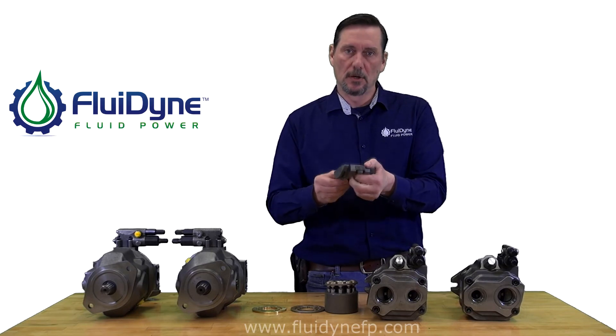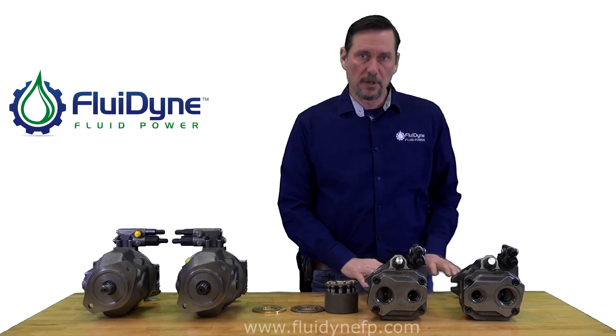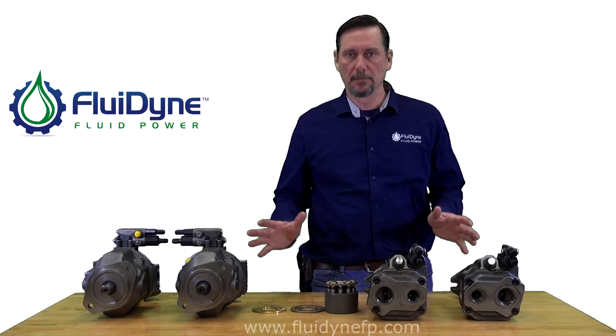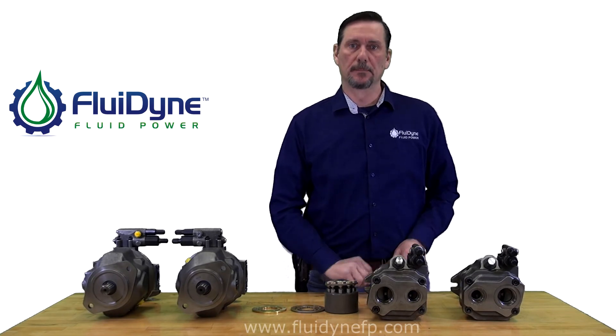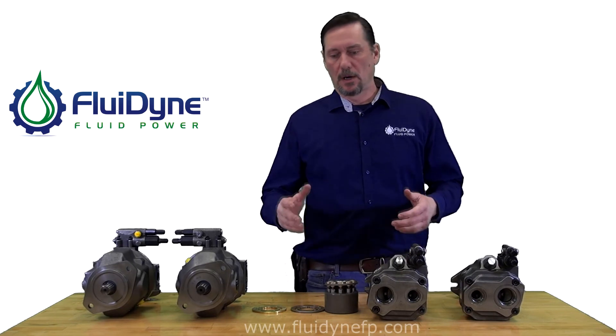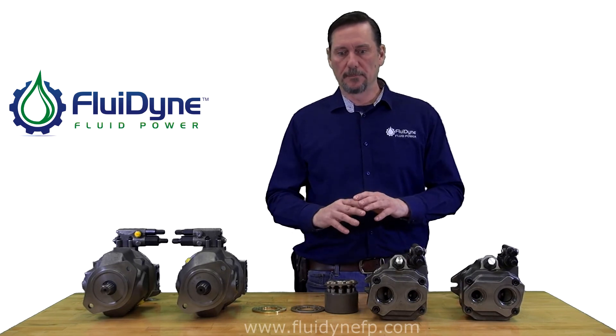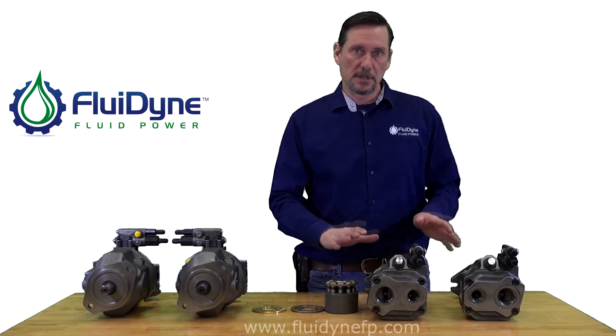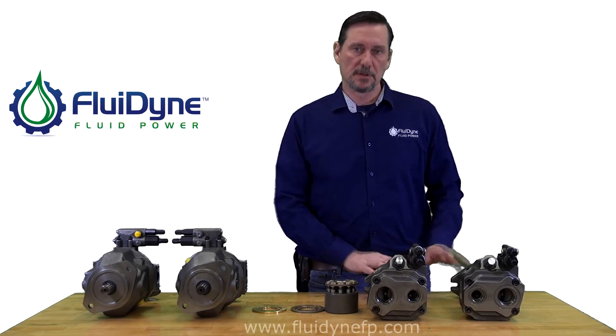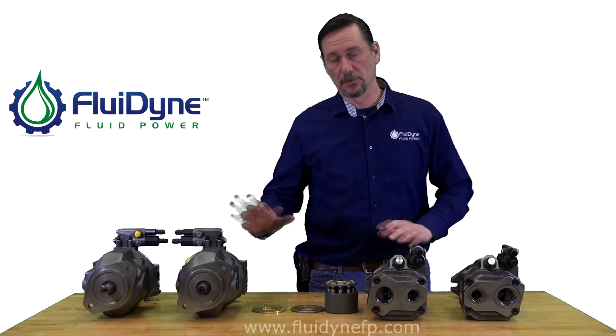So this is a right-handed cradle. Those are rotation-specific, so if you're rebuilding a pump or trying to change rotation, you're going to want to make sure you get all three components: the valve plate, the lens plate, and the cradle. Any other repair parts are kind of interchangeable, like the rotating group. There are differences between the bearings and the seals, so you will have to determine if they're 52 or 31 design.